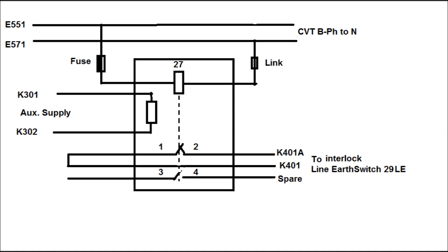The CVT B phase to neutral has been shown by E551 and E571, and is also fed to the coil of the under voltage relay by means of fuses and links. Two contacts — one NC (contacts 1 and 2) and one NO (contacts 3 and 4) — have been shown in this figure. Auxiliary supplies are also given to the under voltage relay by means of K301 and K302.